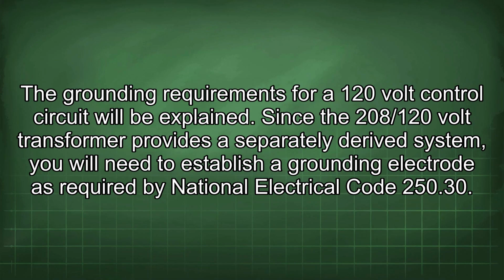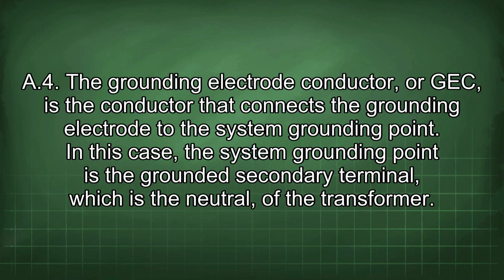The grounding requirements for a 120-volt control circuit will be explained. Since the 208/120-volt transformer provides a separately derived system, you will need to establish a grounding electrode as required by National Electrical Code 250.30(A)(4). The grounding electrode conductor, or GEC, is the conductor that connects the grounding electrode to the system grounding point. In this case, the system grounding point is the grounded secondary terminal, which is the neutral of the transformer.